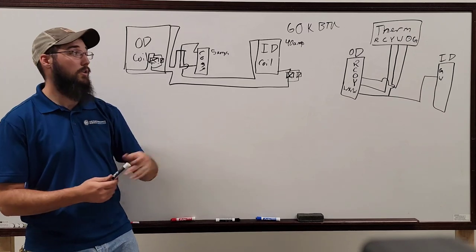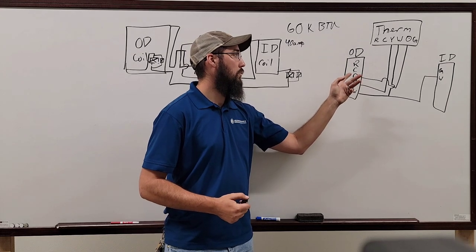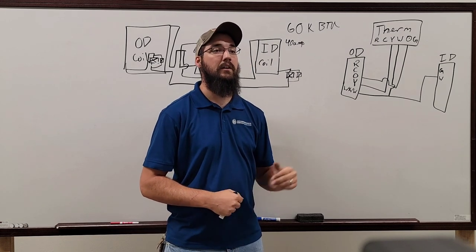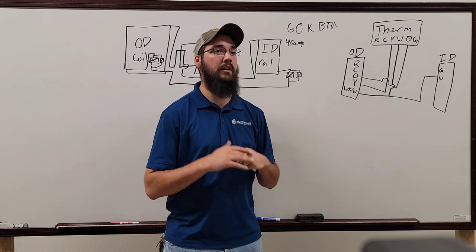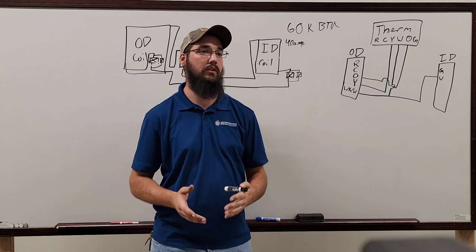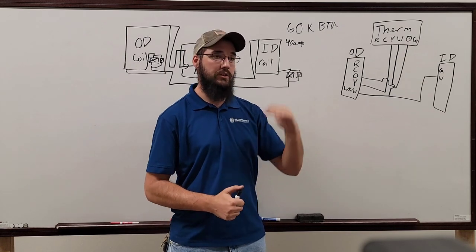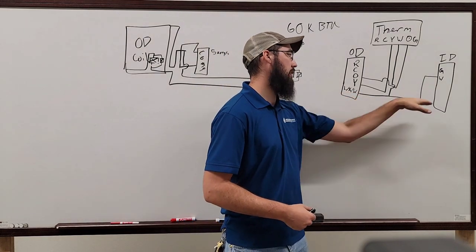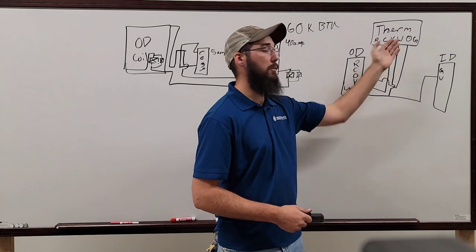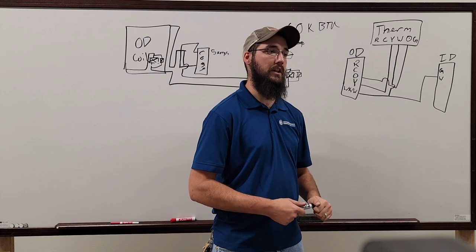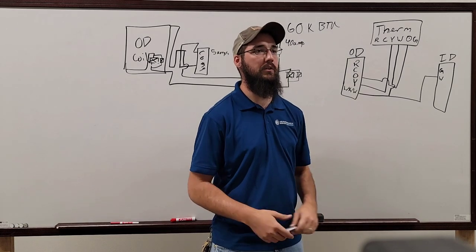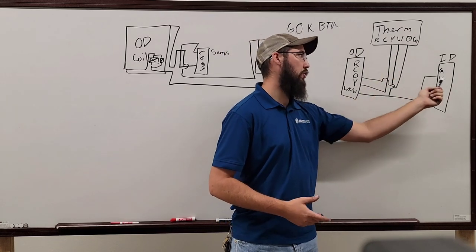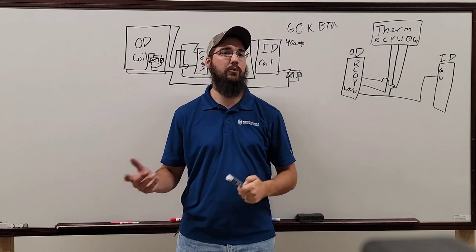And again, so in that scenario, once you get below 20 degrees outside, the outdoor unit says, okay, it's too cold of an ambient. I'm no longer efficient to run. It's a waste of time for me to turn on. It will shut itself off and lock out on low ambient. And then it will automatically bring on W. Again, the thermostat will never see it. It does not know that that's happening. Granted, we have communicating thermostats today. I'm not referencing those systems whatsoever. I'm saying on a standard system, that thermostat has no control at that point, knowing that the outdoor unit did that.